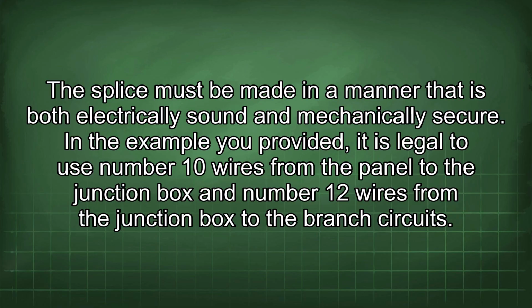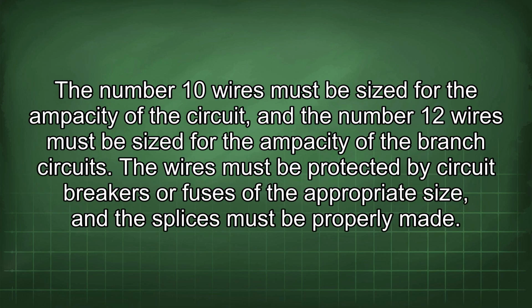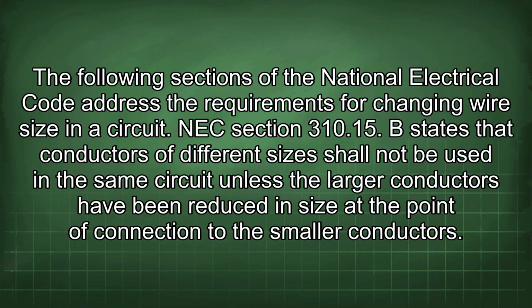In the example you provided, it is legal to use number 10 wires from the panel to the junction box and number 12 wires from the junction box to the branch circuits. The number 10 wires must be sized for the ampacity of the circuit, and the number 12 wires must be sized for the ampacity of the branch circuits. The wires must be protected by circuit breakers or fuses of the appropriate size, and the splices must be properly made. The following sections of the National Electrical Code address the requirements for changing wire size in a circuit.